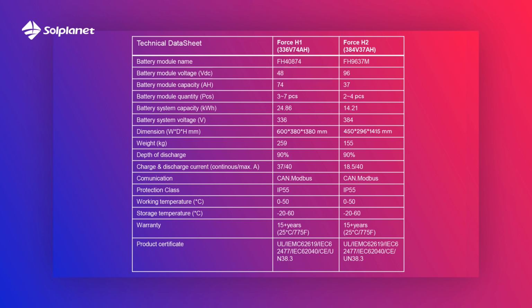The H2 version is higher. One module has 96 volts. Difference between H1 and H2. H1 has 48 volts. So we will have 3 to 7 modules. Max capacity energy banks will be 24.8 kilowatt hours. H2 has 96 volts. So we will have 2 to 4 modules. Max capacity energy bank would be 14.2 kilowatt hours.